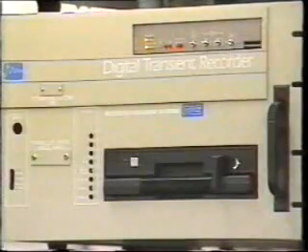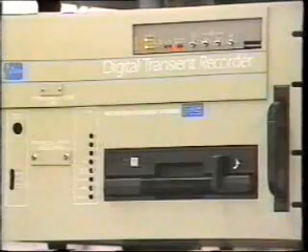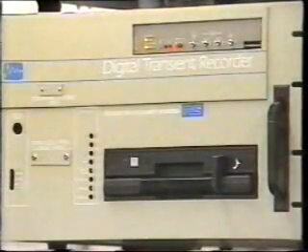In recent years, most of the fault analysis systems installed are of the digital type, generally known as digital fault recorders. This type of system usually allows for a greater number of monitoring inputs. The measurement, that is, sampling, is made simultaneously from all inputs, and a very high rate of sampling is achieved, say 6,000 measurements per second.